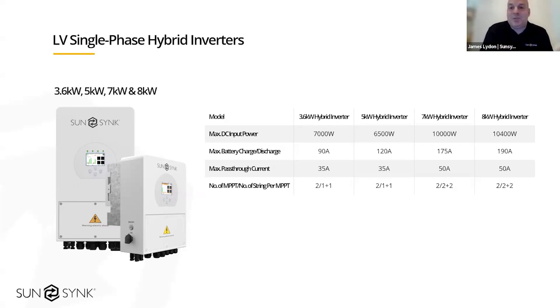And let's say you've got 6 kilowatt of PV on the roof. The max you're going to export, or send to the property, is 3.6, but that other 2.4 we can send to the batteries. So it's keeping it within G98, but it's allowing us to utilize as much roof space as possible. Our 5 kilowatt hybrid inverter has a 6.5 kilowatt MPPT. Our 7 kilowatt hybrid inverter has a 10 kilowatt MPPT.